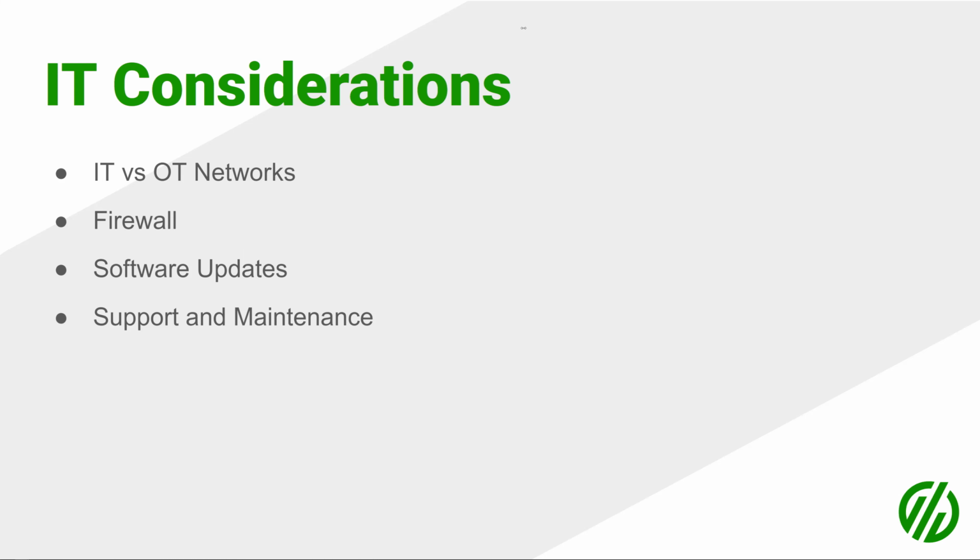And our edge device can act as that bridge. It reaches out to the machine; the machine does not reach out to it. There are no firewall rules where you have to allow the cloud to interface with your internal systems. You can block the edge device from accessing arbitrary services and limit it to just those required by whatever service you're working with. That's fully documented and we can support you on it. But there's no reason for you to open up ports so that the outside can reach in. By allowing the IT network, internet-bound, versus the OT network, machine side, to be segregated, you're going to protect your equipment.